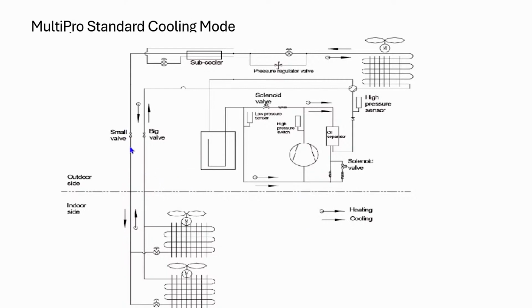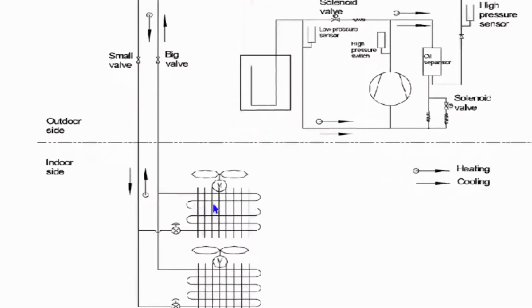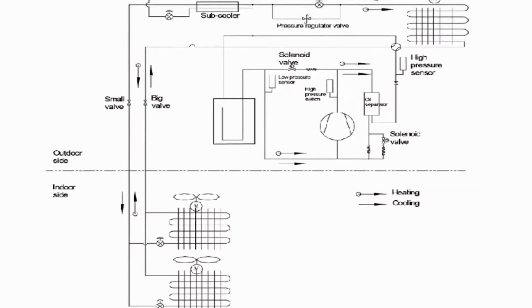In other words, as you can see right here, that is a shared liquid line. The metering device is on the indoor unit on both of these indoor systems, okay? Now, these indoor systems could be a cassette, a ducted unit, an air handler, or a console. We have an array of different indoor unit options. And then you have a common headered gas line that comes all the way back to the machine as well. Now, I know there's some people on here going, man, that'd be nice to have those piping diagrams. Well, you do have access to these piping diagrams. All the piping diagrams I'm going to talk about today come out of the service manual.